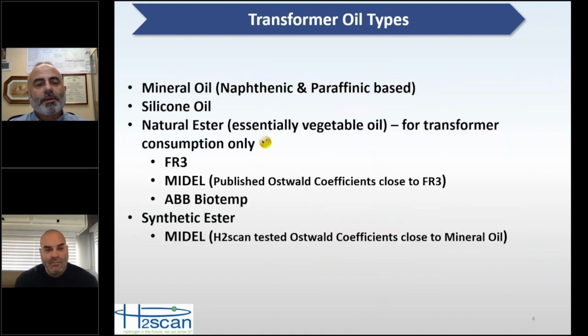So for the different oil types, historically mineral oil has been the primary oil in power transformers and all different types of oil-filled transformers. Naphthenic is normally what's used, but there are also paraffinic oils. Paraffinic oils have a higher amount of wax in them, so they have to be refined to get that wax out, because you don't want your oil glazing over. Silicone oil is popular in certain classes of transformers. Today, natural esters, which are essentially vegetable oil, and I've got a little note there, for transformer consumption only. Even though it's vegetable oil, you don't want to be frying up your tater tots for dinner in the vegetable oil.